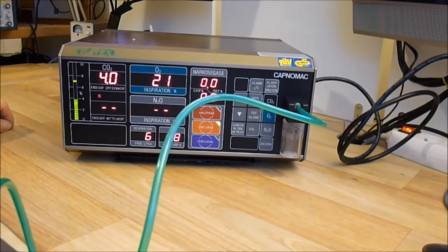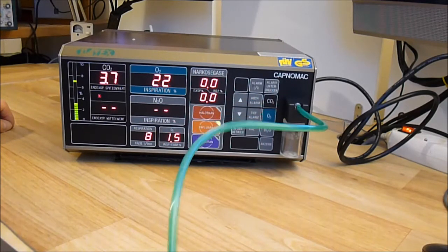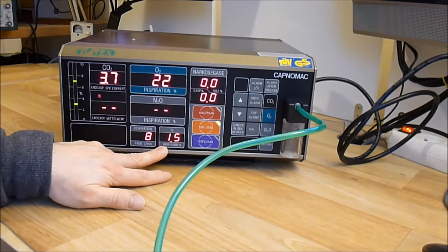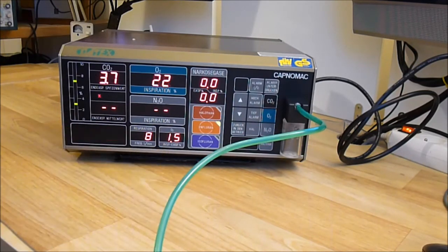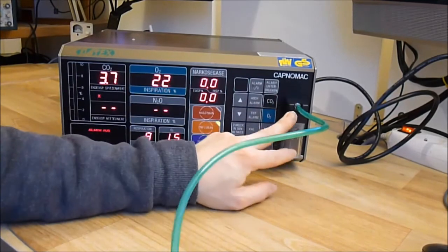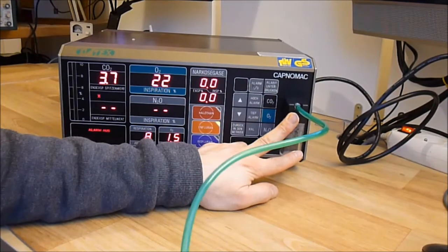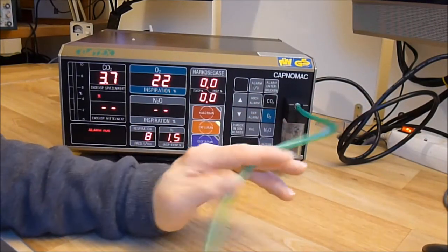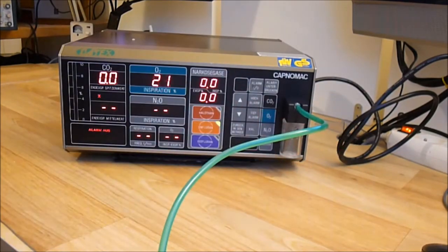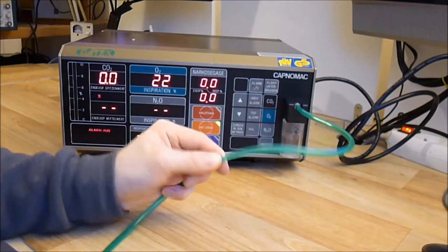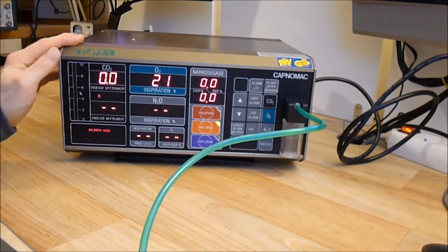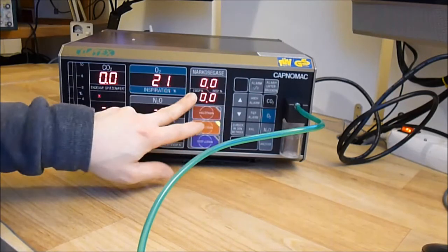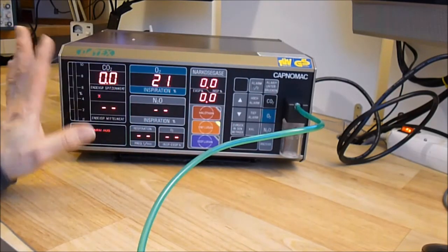So as you can see, it now gives me a number of respirations per minute, the percentage of CO2, difference between the inspiration and expiration. So the way it works is quite strange, because in fact, this air input is so small, it does just measure air pressure difference on the very low air flow in this tube. I do not know the original pick-up tube for it, the size. I believe it is a pick-up tube that is derived directly onto the anesthesia mask, not sure. So it is again an alarm. As you can see, it never measured the N2O, and of course these numbers are at zero. But the other things seem to work, as far as I can tell.